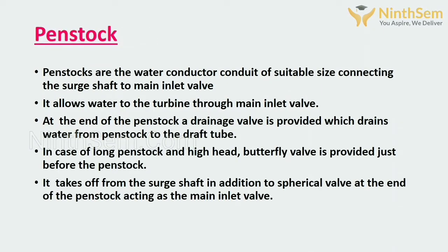Penstock. Penstocks are water conductors of suitable size connecting the surge shaft to the main inlet valve. It allows water to the turbine through the main inlet valve. At the end of the penstock, a drainage valve is provided which drains water from the penstock to the draft tube. In case of a long penstock and high head, a butterfly valve is provided just before the penstock, taking off from the surge shaft, in addition to the spherical valve at the end of the penstock acting as the main inlet valve.